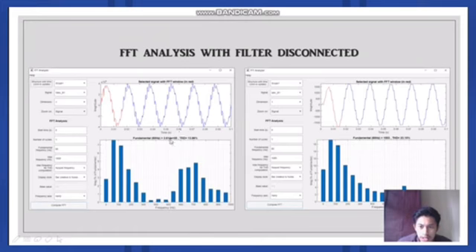From the bar graph here, it shows the THD in the voltage is 13.86%. This value is high and unacceptable in a THD system. Same goes to the current. The total harmonic distortion percentage in this current is 23.15%. So it seems like the voltage value here is very high and unacceptable in a THD system.